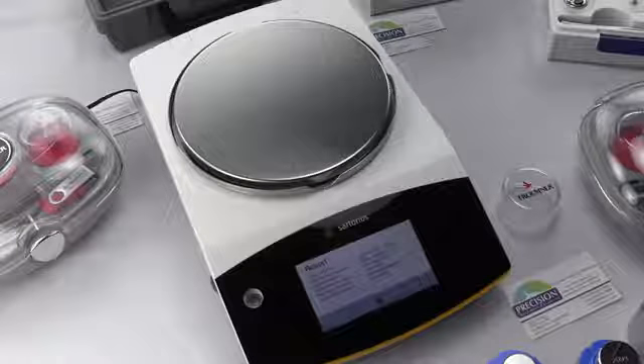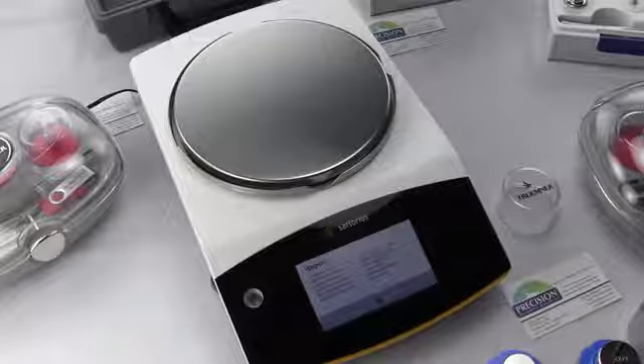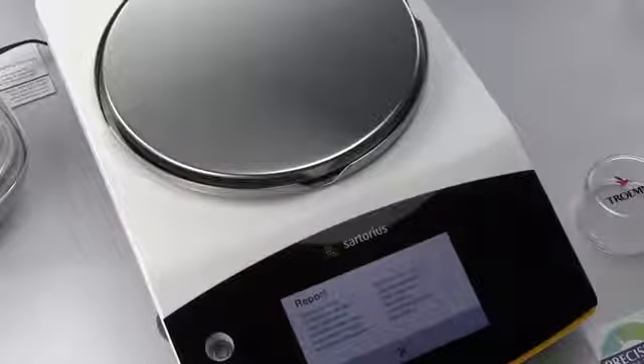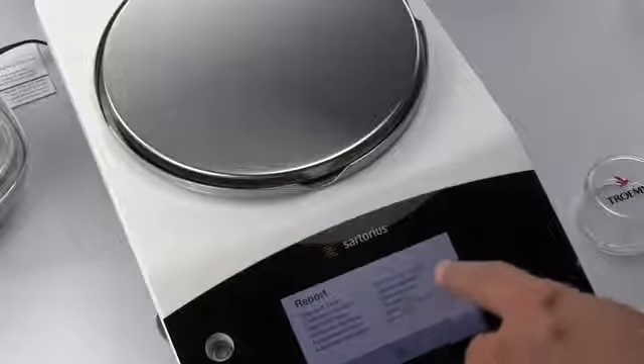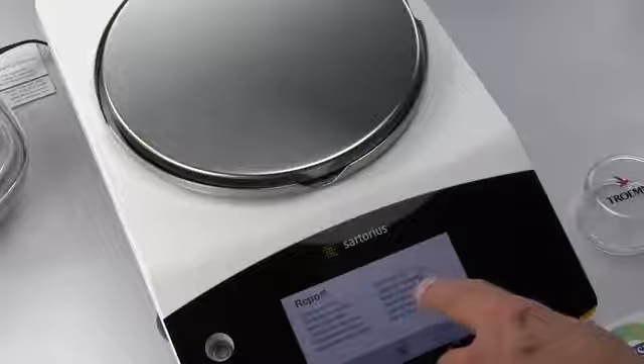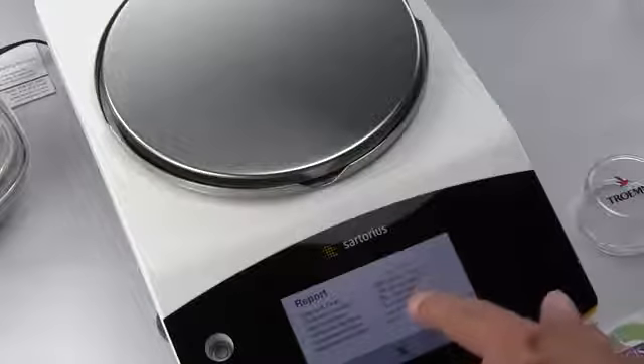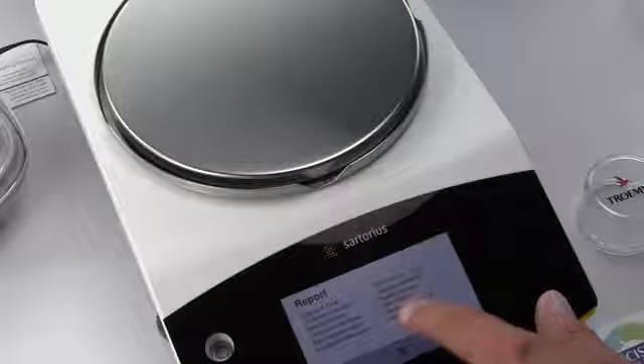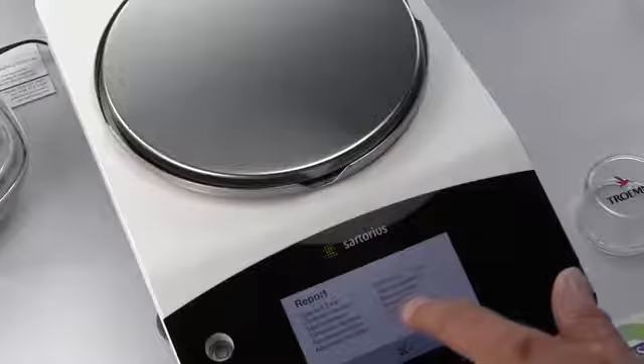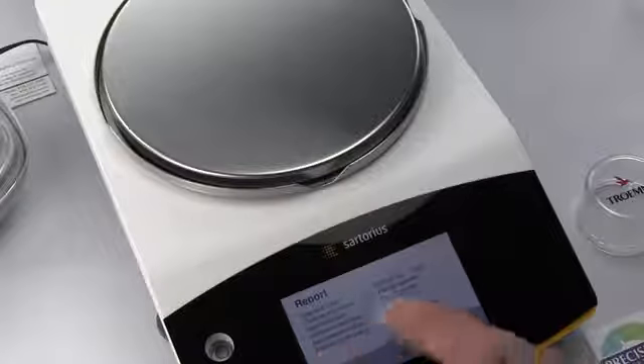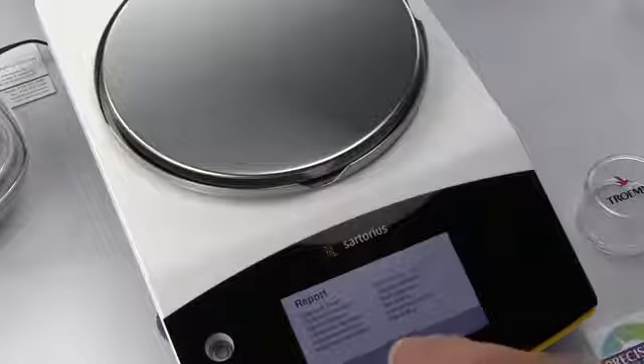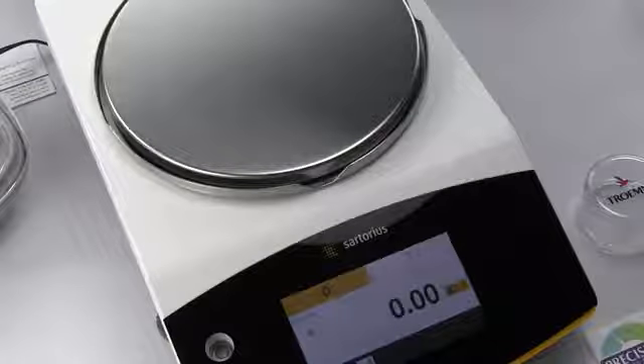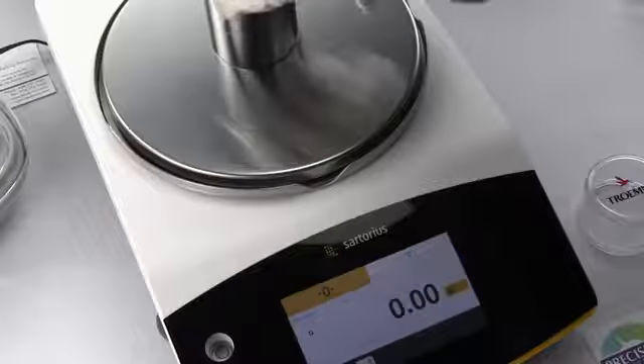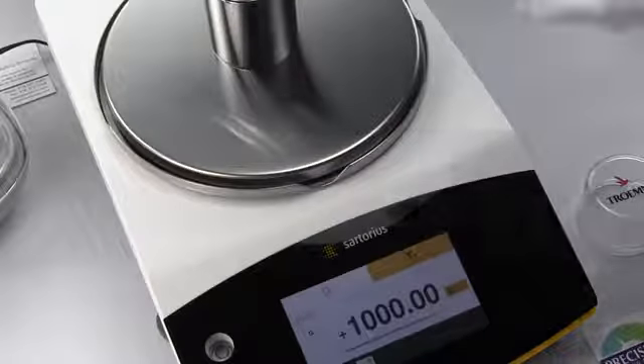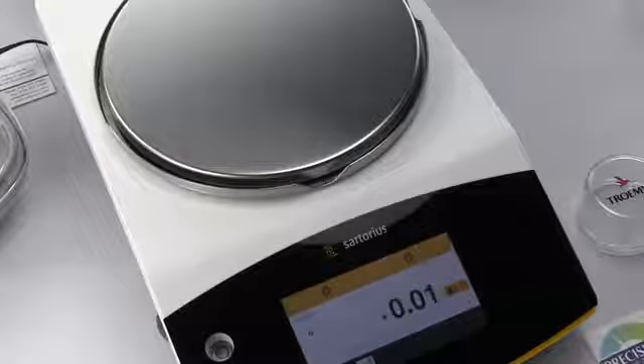Now when the calibration is completed, we can see that we have a report here. In this report, you can see the date and the time. The calibration function was internal calibration. It was started manually. The calibration deviation was 0. The adjustment function was the internal. And the adjusted deviation, since there was no change from the last calibration, was 0.00 grams. And then we just select the X to get out of it. Now the calibration is done.